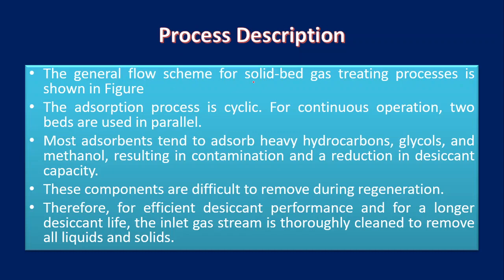The general flow scheme for the solid bed gas treating process is shown here, and the adsorption process is cyclic. So for continuous operation, we need two beds used in parallel, not in series. One bed operates at a time, and when it is saturated, we have to switch over to the second bed.